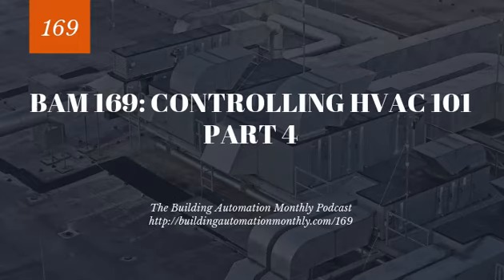So with boilers, you have to maintain a minimum outlet temperature, and you have a maximum outlet temperature as well, right? And the reason you can't go below the minimum is that you don't want to condense, and the reason you can't go above the maximum is because you'll start to do boiling and things like that. Temperature drop needs to be maintained across the supply and the return. You don't want to have a huge temperature differential between supply and return, that can actually be bad.